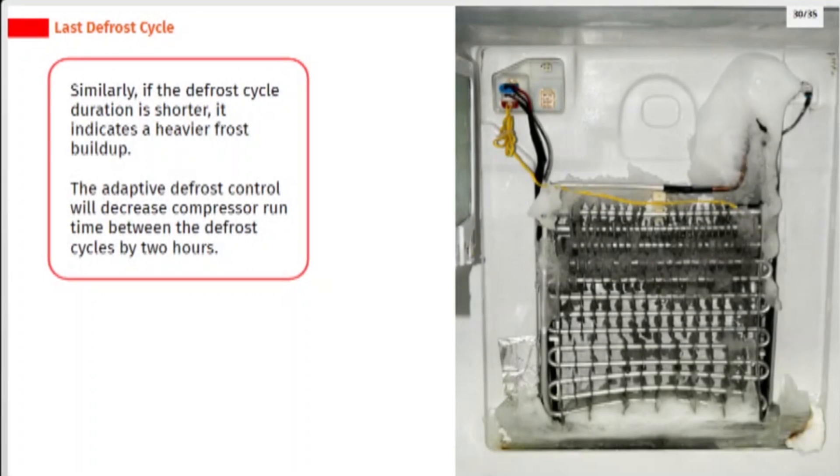Similarly, if the defrost cycle duration is shorter, it indicates a heavier frost buildup. The adaptive defrost control will decrease compressor run time between the defrost cycles by two hours.